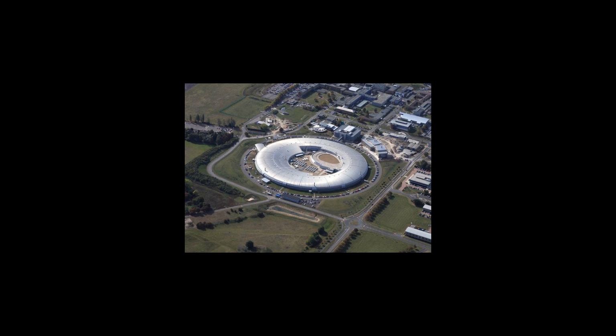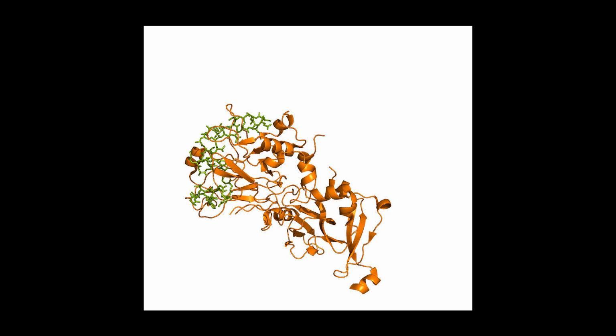The beamline includes X-ray optical devices which control the bandwidth, photon flux, beam dimensions, focus, and collimation of the rays. The optical devices include slits, attenuators, crystal monochromators, and mirrors. The mirrors may be bent into curves or toroidal shapes to focus the beam.